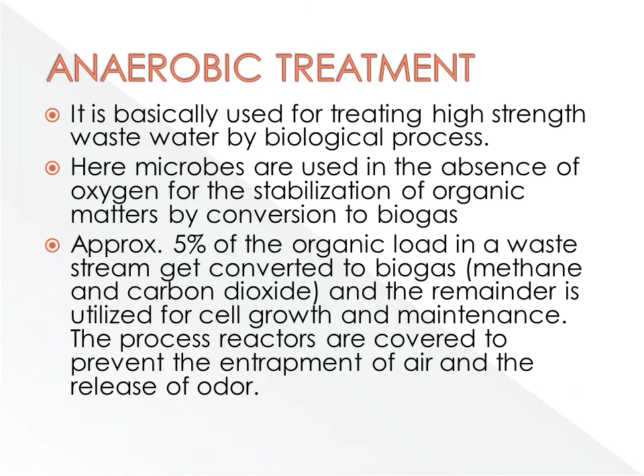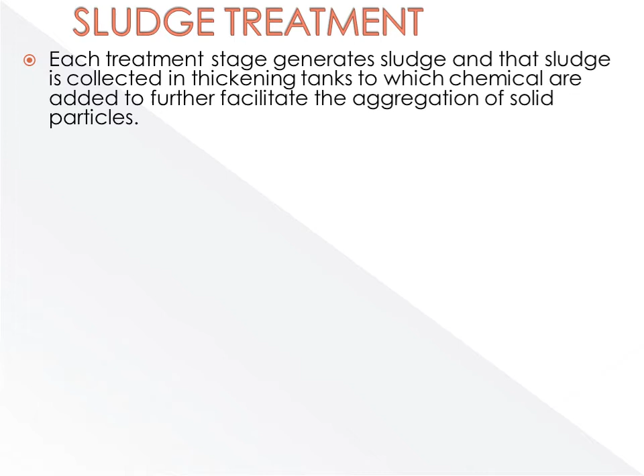Sludge treatment. In all the treatments that have been given to the wastewater, like preliminary treatment, primary treatment, secondary treatment, or we can say mechanical, physiochemical, or biological treatment, in all these treatment processes, all the material that settles down or sediments at the bottom is termed as sludge, and that sludge is collected in thickening tanks to which chemicals are added to further facilitate the aggregation of the particles that are present in the sludge, or to make that sludge more compact so that it can be further used for other purposes.